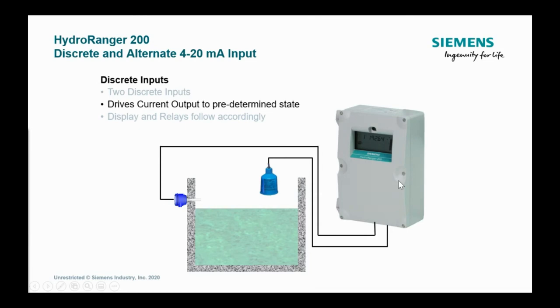So then you know, oop, I'm at a high-high, turn on all the pumps, turn off all the pumps, shut the valve, open the valve, whatever needs to happen in your control system. But this backup level override is kind of a point-level safety system that you can then drive the output to whatever you define. Maybe you want to drive it to a low if you hit a particular point. It depends on really what your control scheme is. There is another parameter in there that you can adjust the time delay on that. So if it trips that switch, wait 5 seconds and then do it. So you can take out some transients if you have maybe waves that splash in there or something like that.